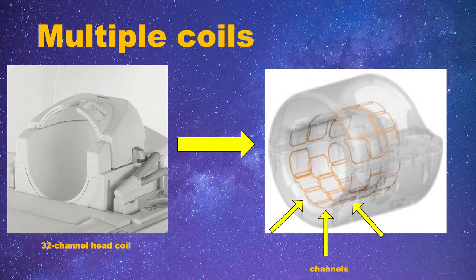They work together to give us an MRI image. But in fact, each of these coils can acquire a complete image. So why do we need so many coils? One short answer is because MRI signals are always corrupted by noise, and the signal-to-noise ratio or SNR is relatively low.